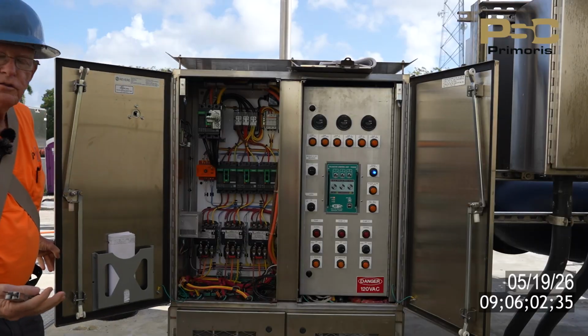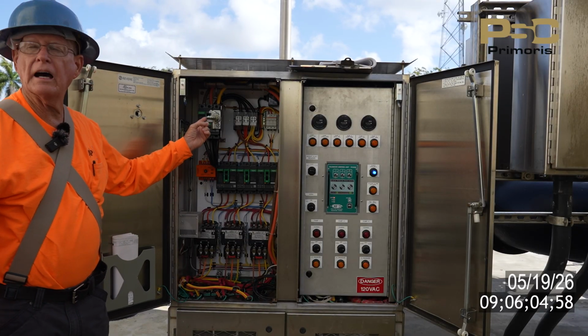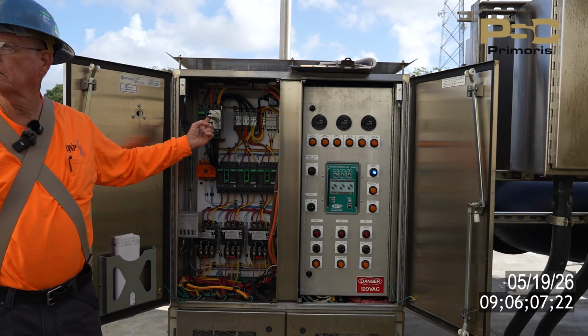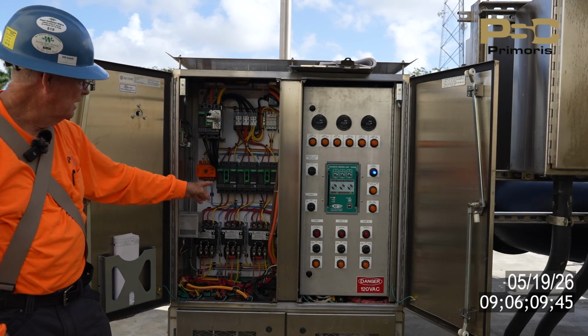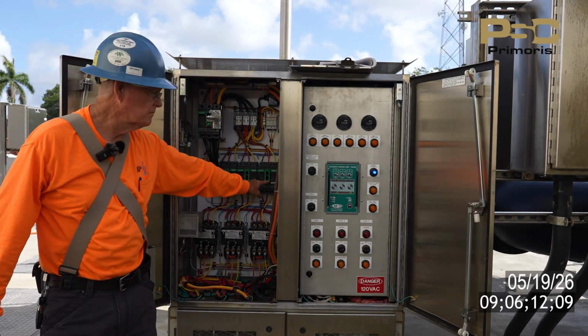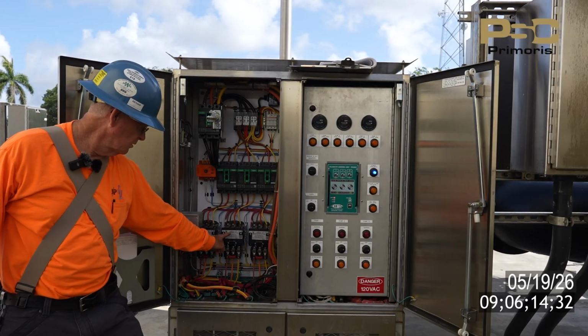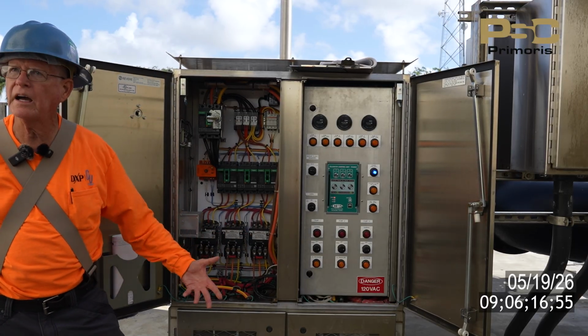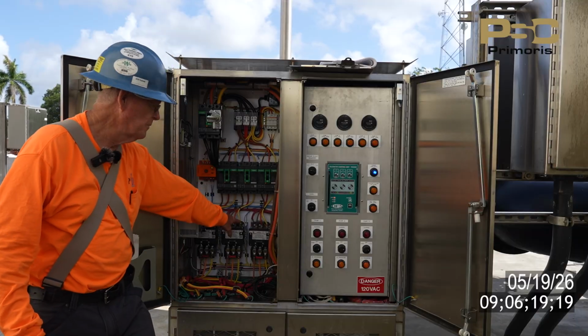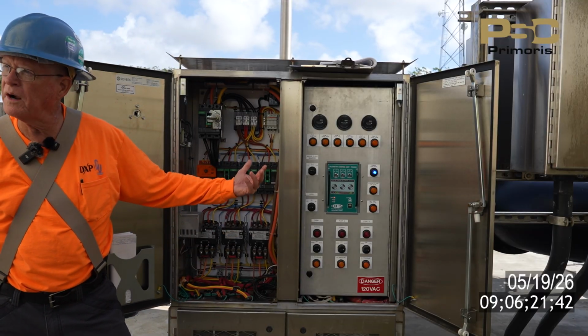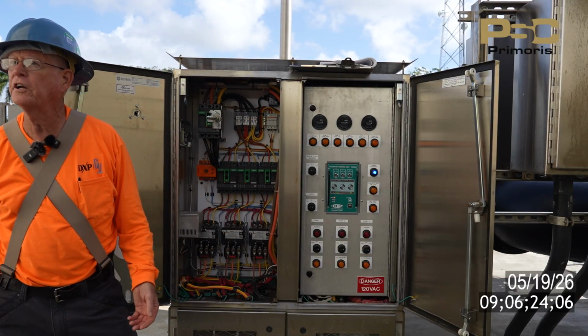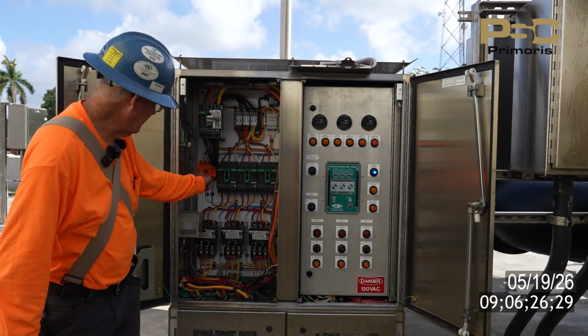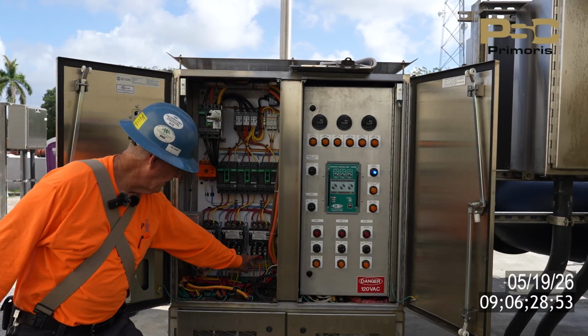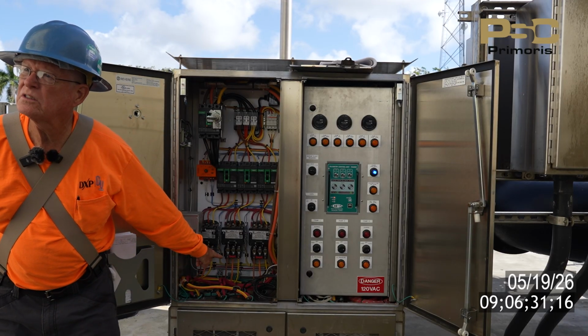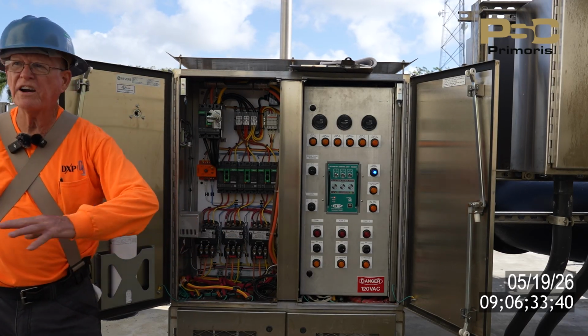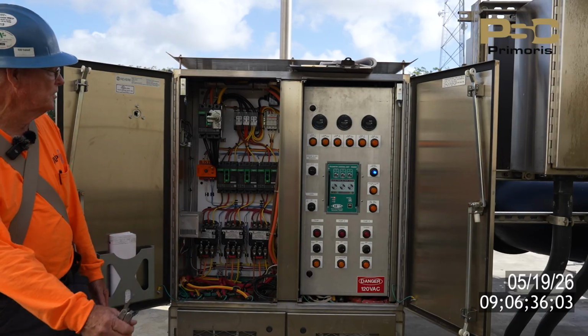Normal situation: I've got the primary circuit breaker that turns power on to the entire panel. I've got individual pump breakers, and individual contactors for each pump so they can run. So if you had to pull number 2, you just turn power off, pull number 2, do whatever you need to do, put it back on, and you're good to go again. Just normal, phase monitor over there. They all have thermal overloads. Everything's standard on that.